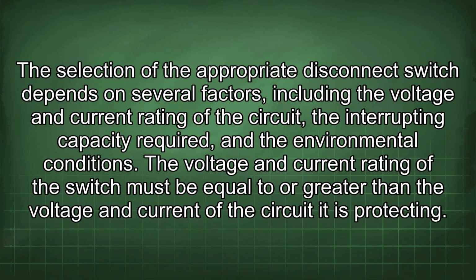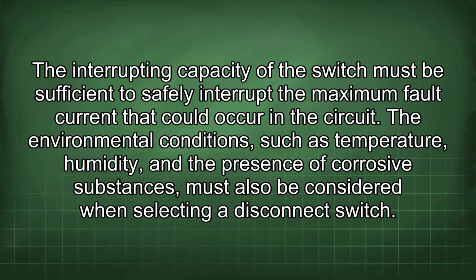The selection of the appropriate disconnect switch depends on several factors, including the voltage and current rating of the circuit, the interrupting capacity required, and the environmental conditions. The voltage and current rating of the switch must be equal to or greater than the voltage and current of the circuit it is protecting. The interrupting capacity of the switch must be sufficient to safely interrupt the maximum fault current that could occur in the circuit.